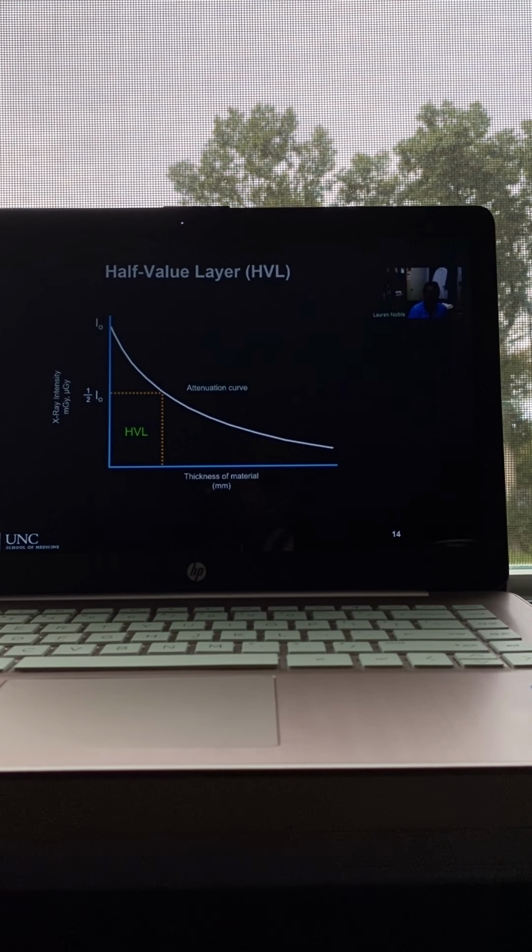However, most medical physicists aren't actually plotting this anymore because the X-ray equipment, the devices that are used to do quality control, can actually calculate this internally. So you can make an exposure, and the piece of equipment does the computations internally and spits out a half value layer.